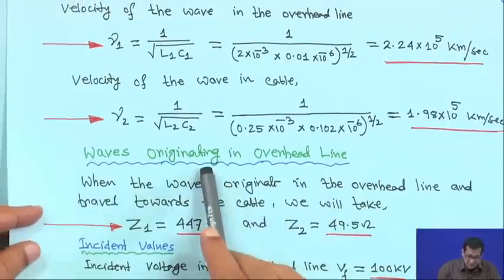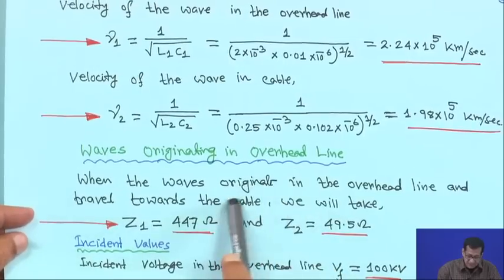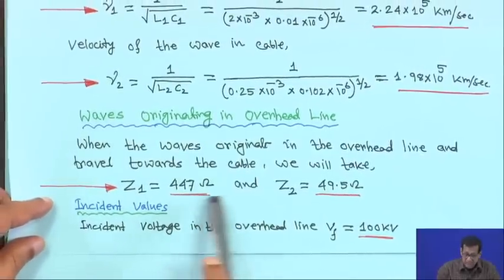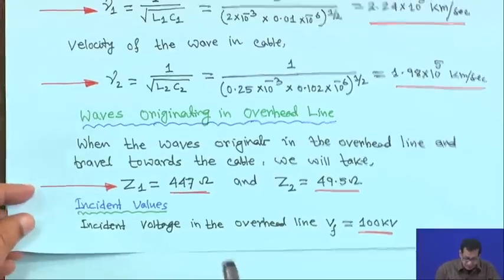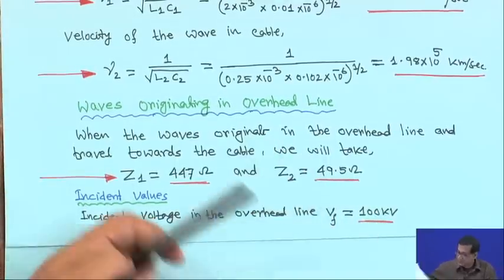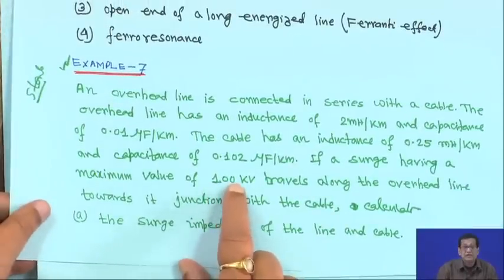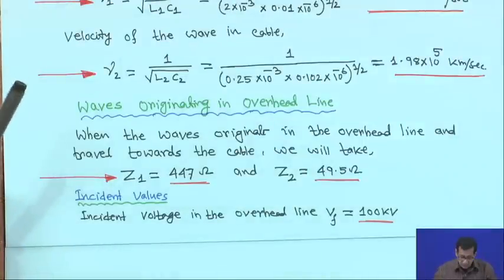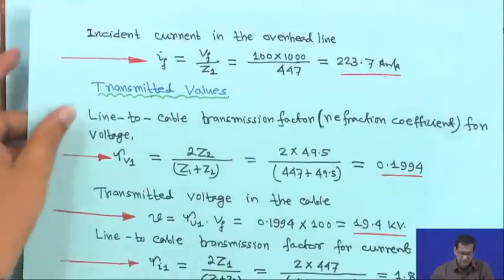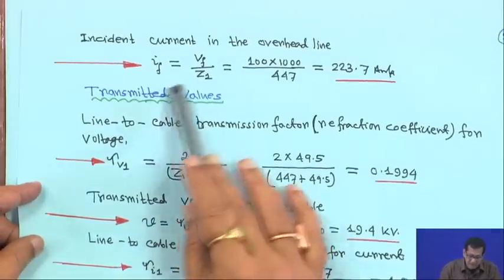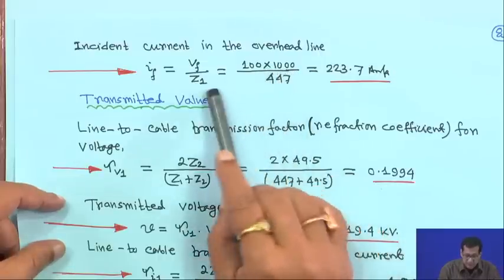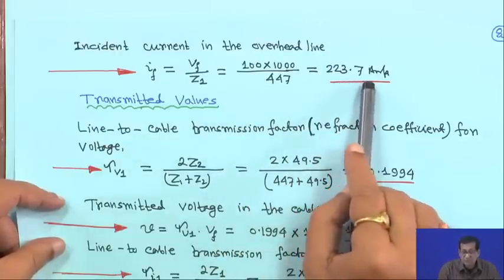Now, for waves originating in the overhead line: Z1 equals 447 ohms and Z2 equals 49.5 ohms. The incident voltage in the overhead line is given as 100 kV. So incident voltage Vf equals 100 kV, and incident current If equals Vf upon Z1, which is 100,000 divided by 447, giving 223.7 amperes.